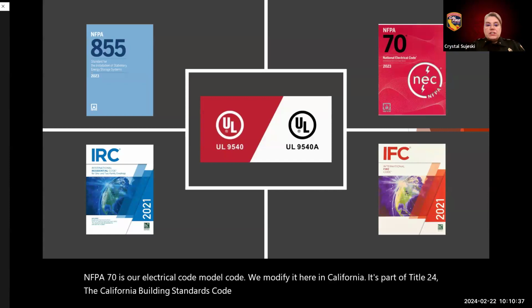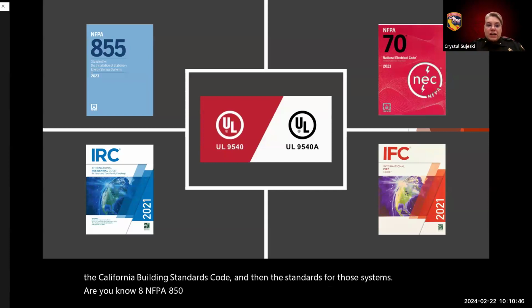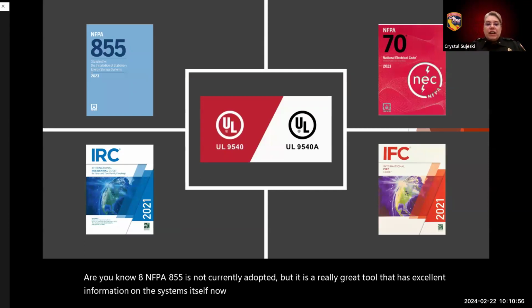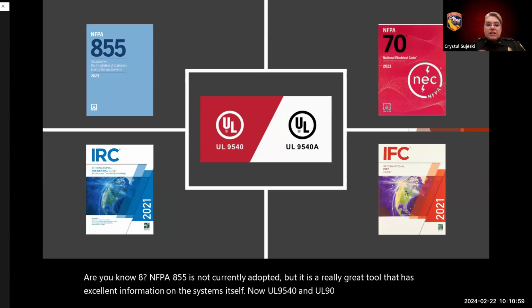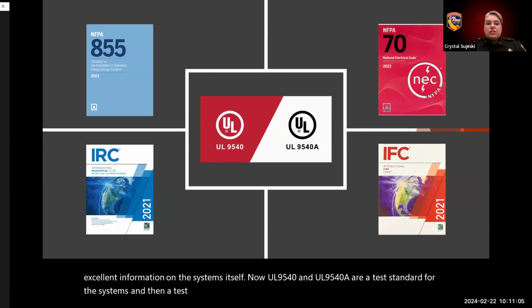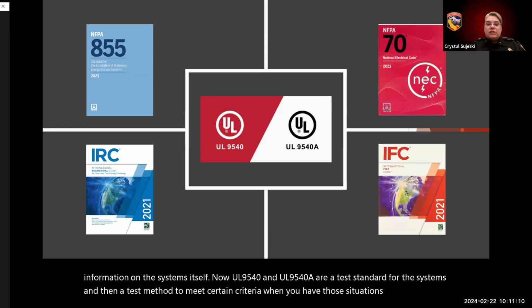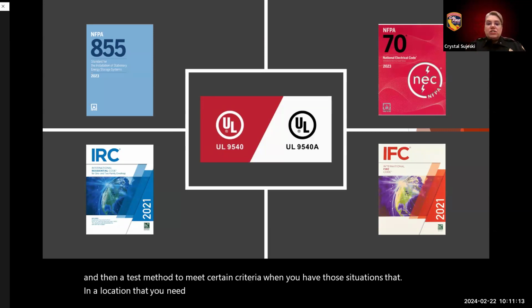And the standards for those systems: NFPA 855 is not currently adopted, but it's a really great tool with excellent information on the systems themselves. UL 9540 and UL 9540A are a test standard for the systems, and a test method to meet certain criteria when you have situations in a location that require additional information for the system.